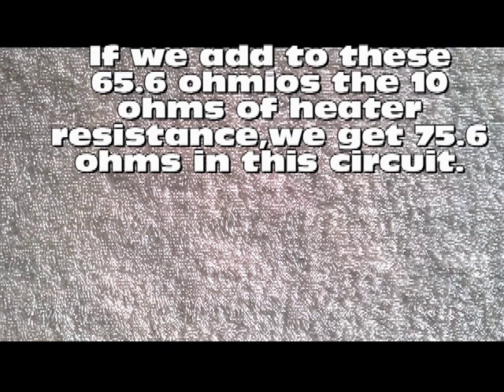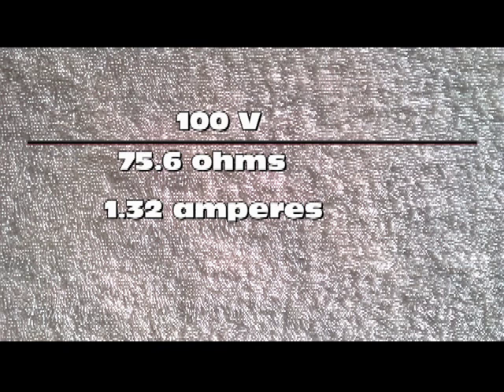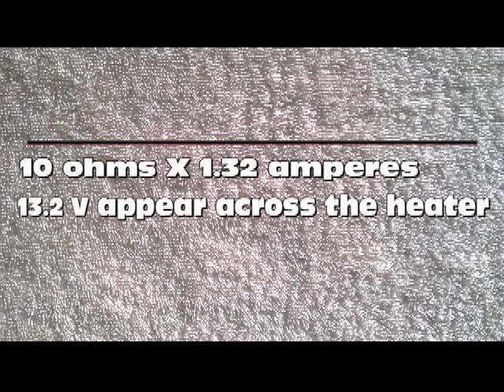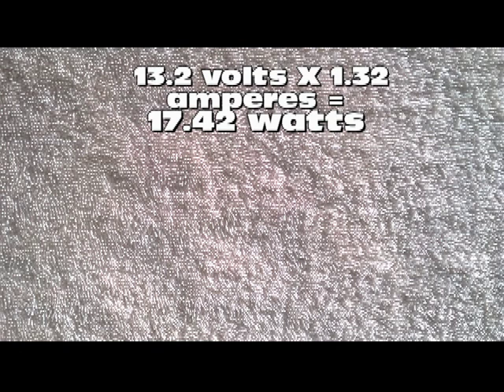If we connect the same heater to the end of the line and add the resistance of the 10-ohm heater to the resistance of the 65.6-ohm cable, we will have a total of 75.6 ohms. Using Ohm's law, 100 volts applied to a load of 75.6 ohms will produce a current of 1.32 amps. The heater, which has a resistance of 10 ohms, will be receiving only 13.2 volts at its input terminals. The power delivered will be 13.2 volts multiplied by 1.32 amps, giving only 17.42 watts — far too little for it to work.